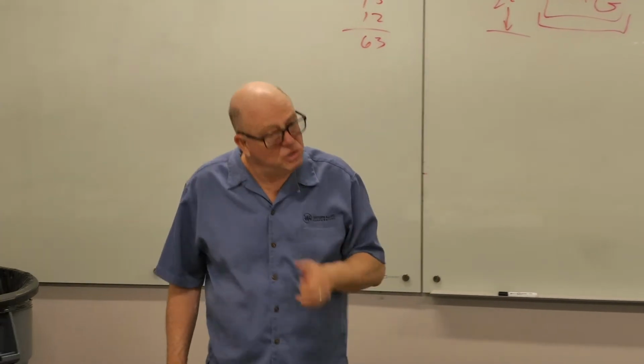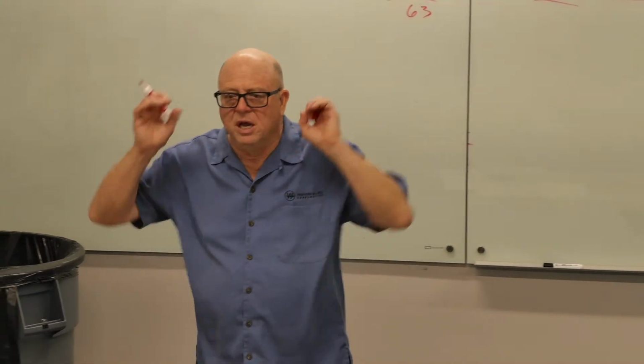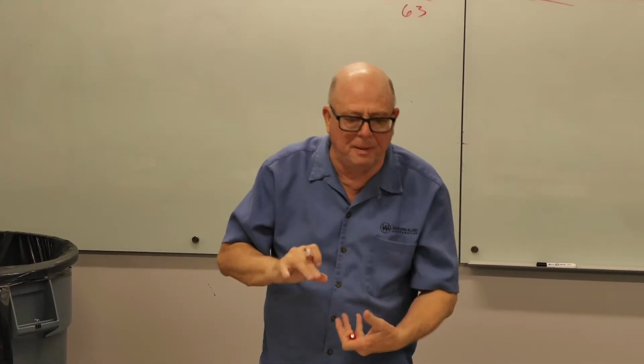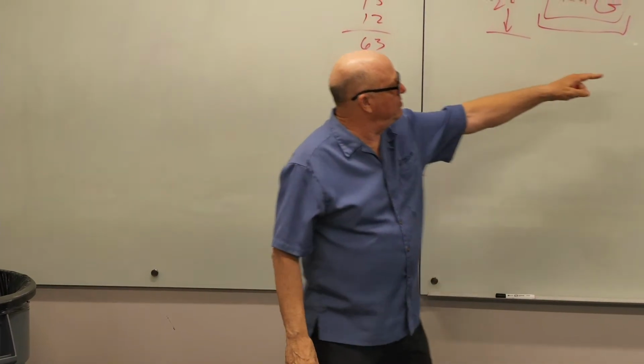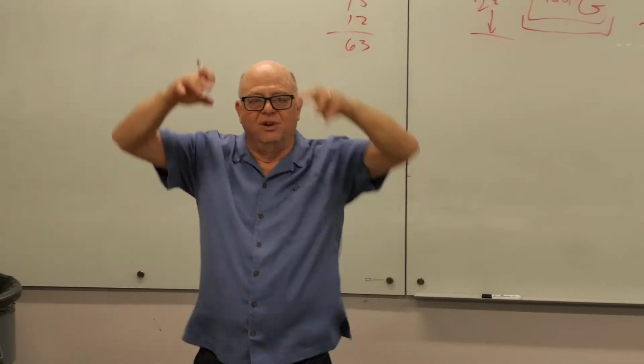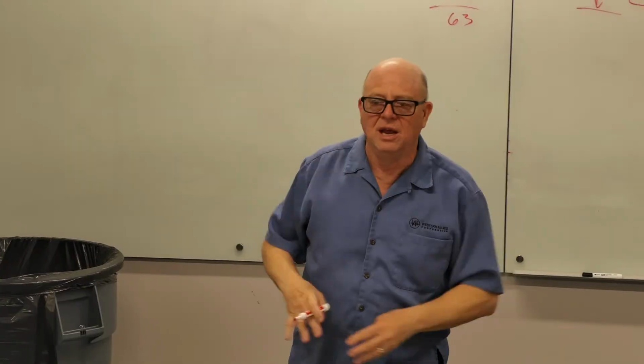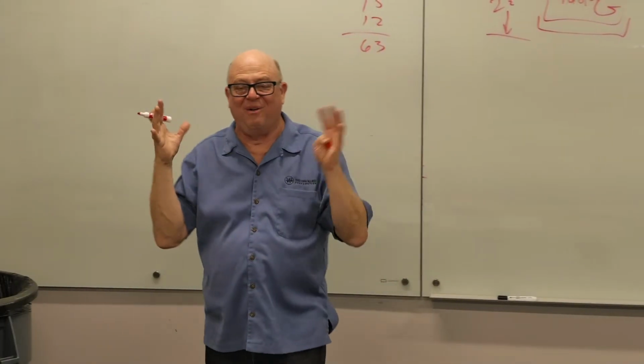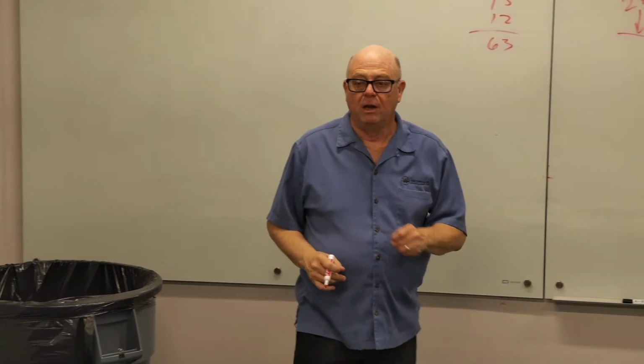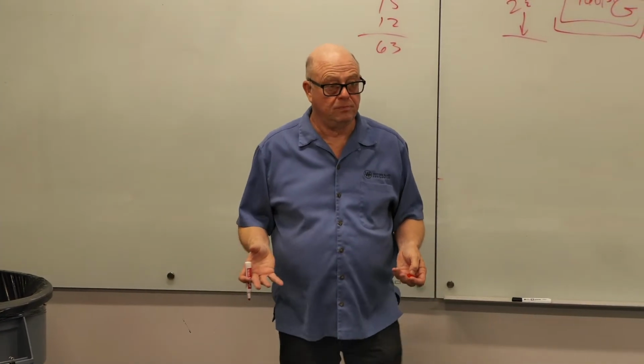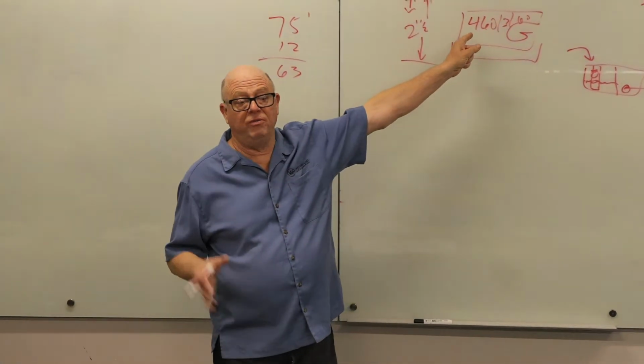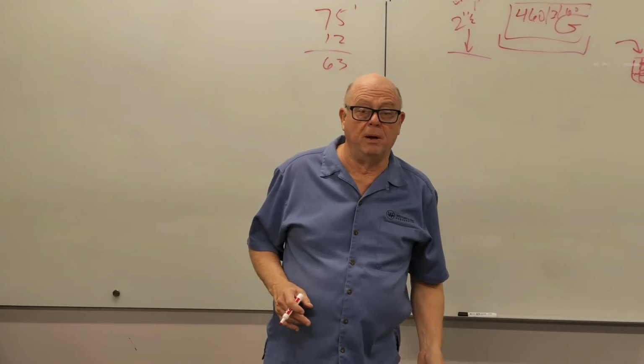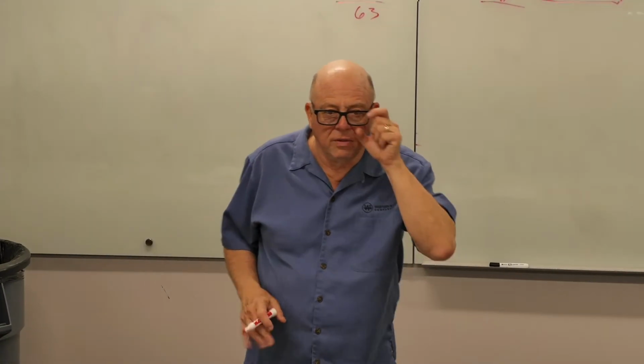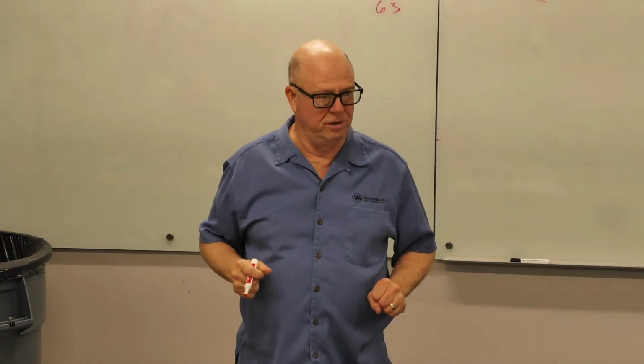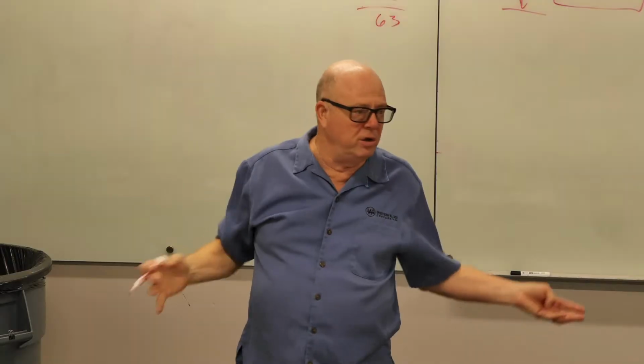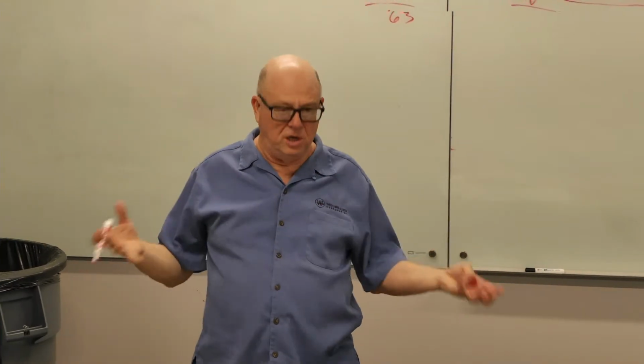Well, there should be, but manufacturers, like everybody else, are skimping down to the bare minimum they need to get by. And what you don't want is every time the condensate pump turns on, your voltage drops from 24 volts down to about 17. That's not good for the circuit board and how it operates. Okay? So you might have to run a separate electrical service. And you certainly will if you wanted, for whatever reason, let's say, to use a 115 volt condensate pump. As you might expect, the higher the voltage of the condensate pump, the more head it'll push. If you've got to push a bunch of head, you probably aren't going to make it with a 24 volt condensate pump. You're probably looking at using 115.